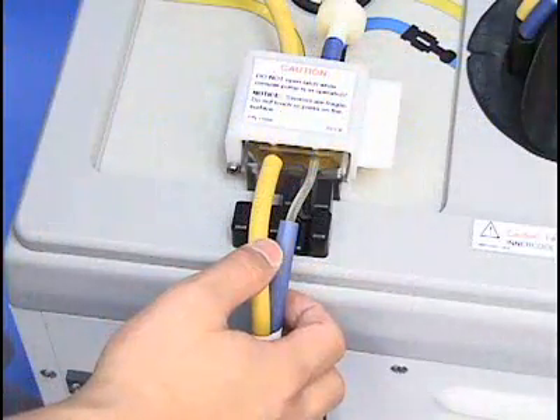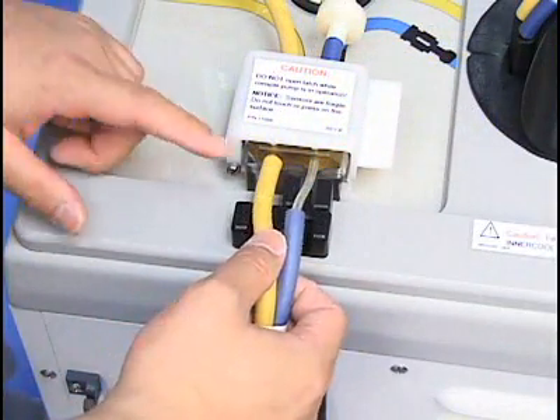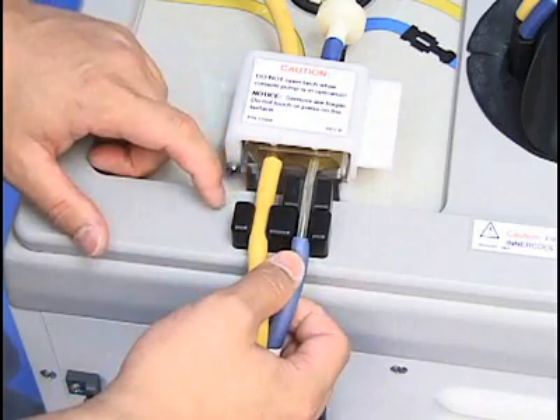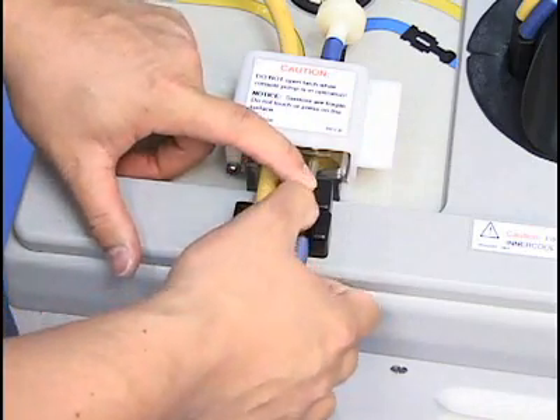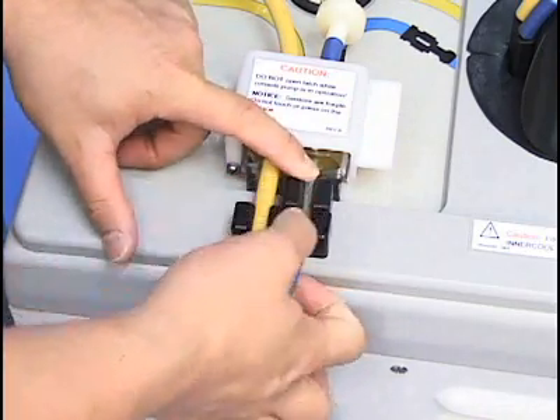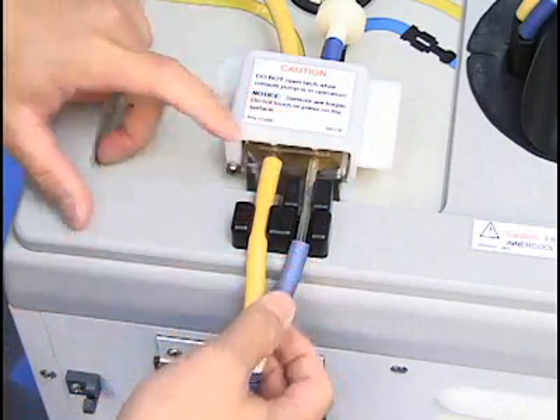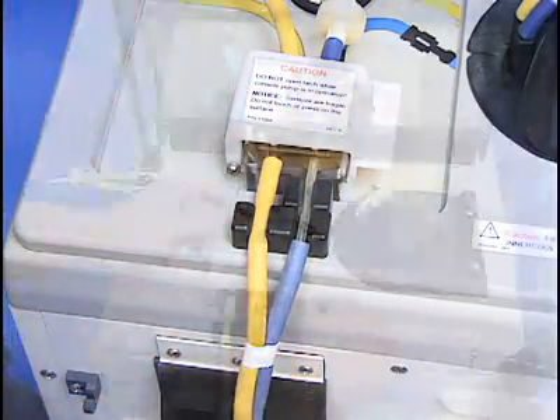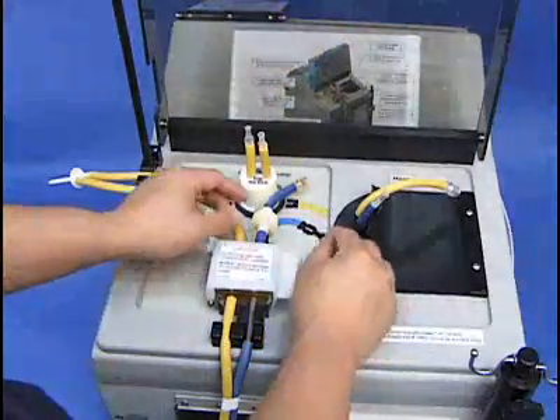Next, place the length of uninsulated tubing through the bubble detection channel. This should be placed snugly into the channel to avoid getting air signals. Then make all other connections indicated on the installation diagram.